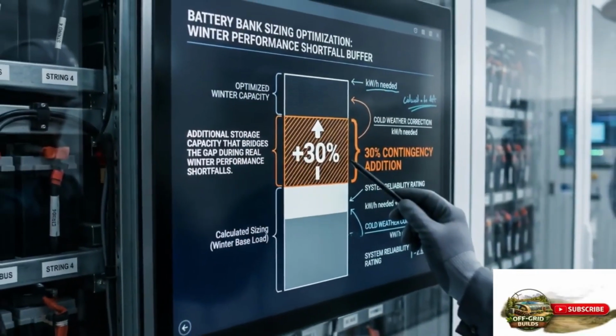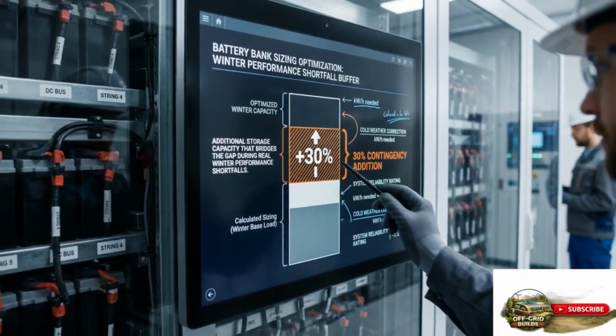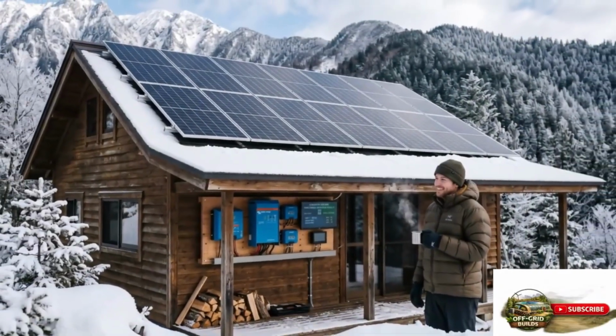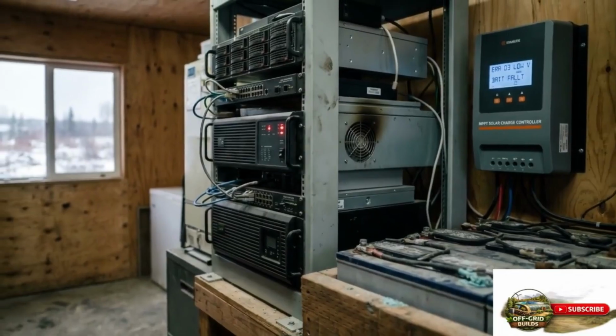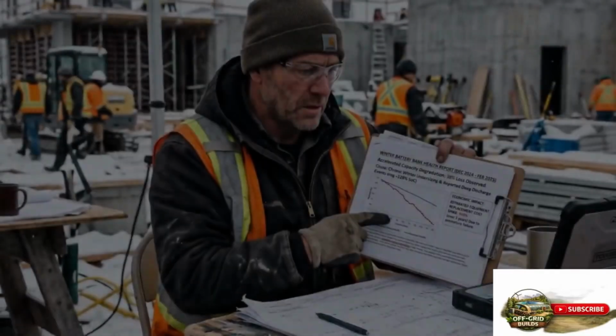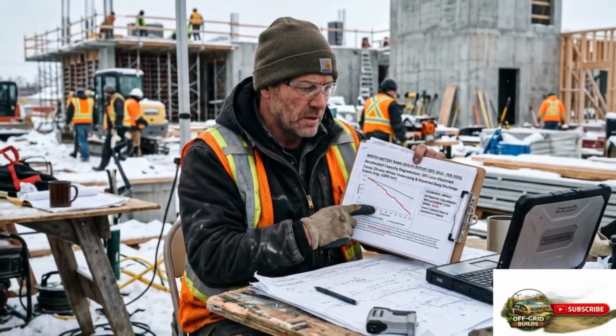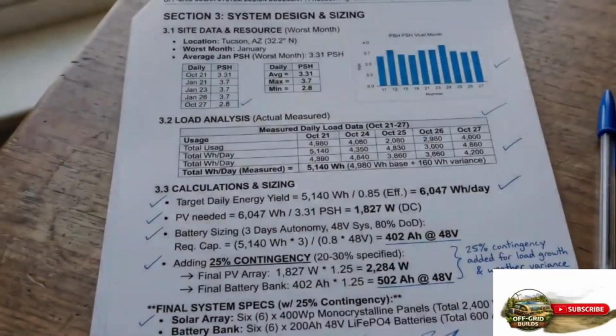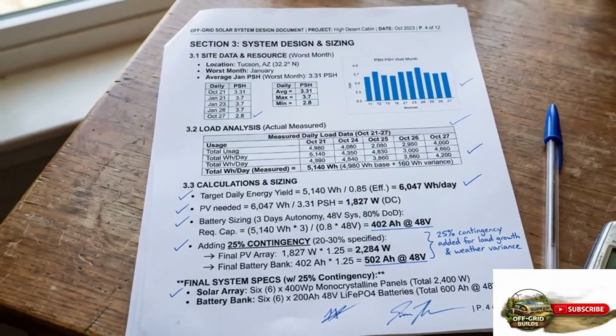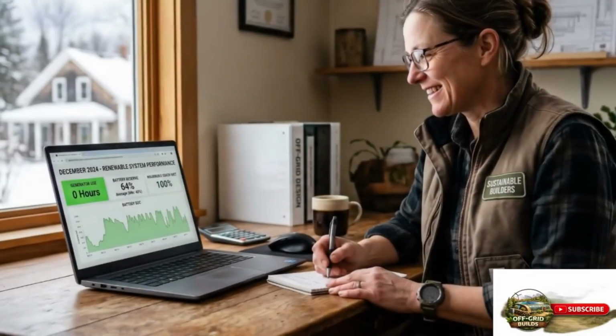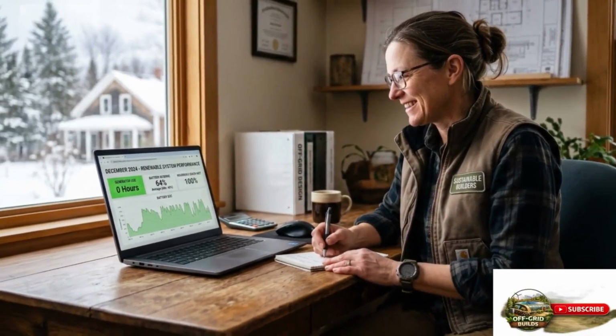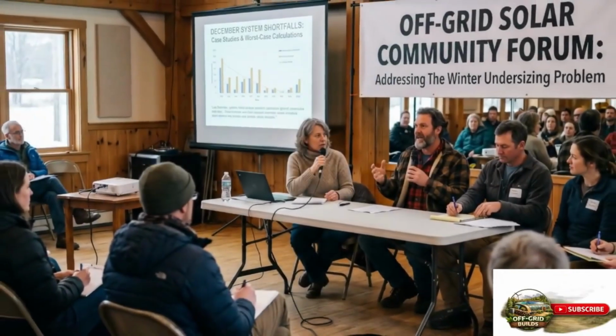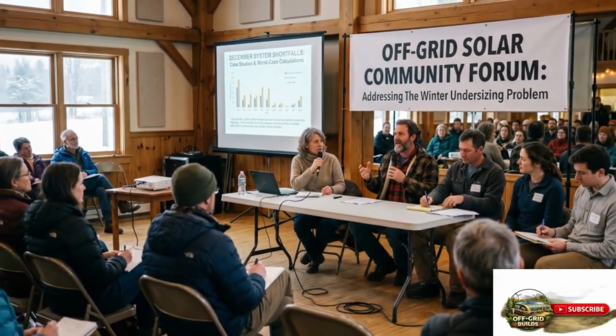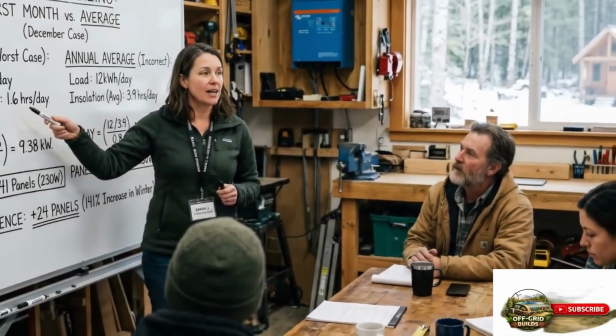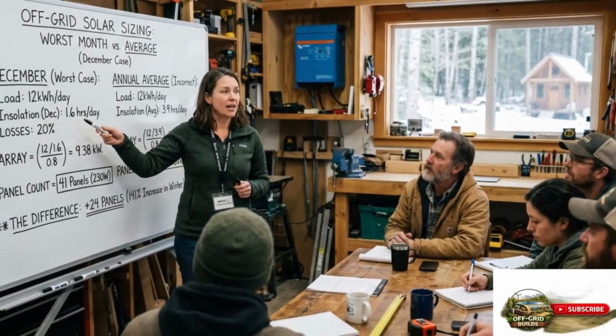This is the scenario that causes off-grid households to run their generator for weeks every December and January, which was never part of their plan. The correct approach is to size your solar array and battery bank for your worst month solar resource, not your annual average, and to calculate your daily household consumption honestly using the actual loads that will be in the home rather than an idealized, efficient lifestyle that may not match the reality of your household's actual behavior. Add 20 to 30% contingency to both your panel count and your battery capacity beyond what worst-case calculation requires, and you have a system that performs reliably through every month of the year rather than a system that is technically adequate on average but struggles through every winter.